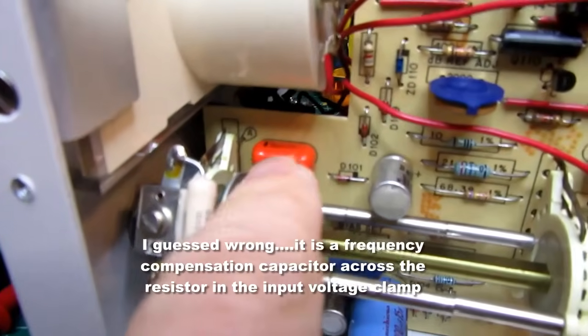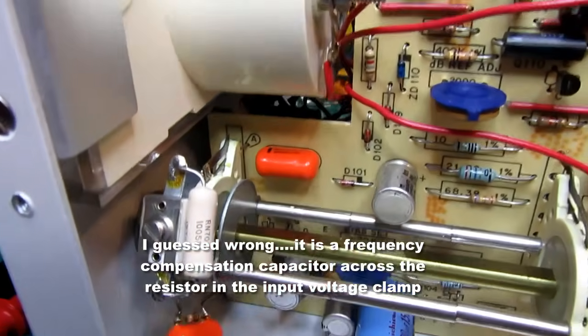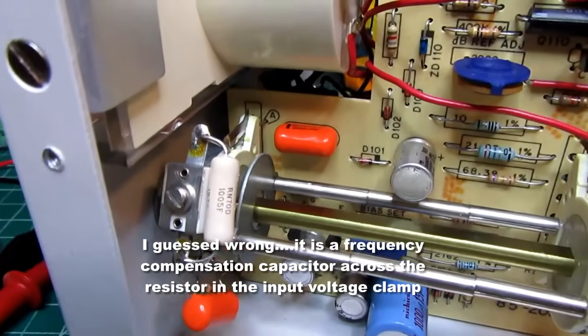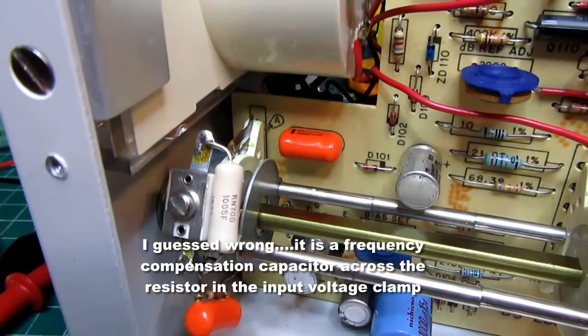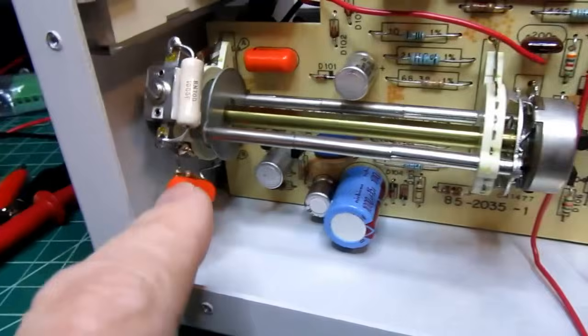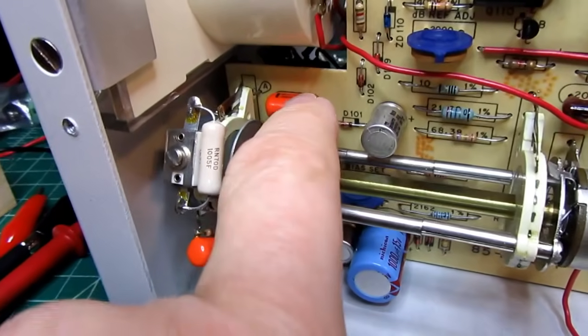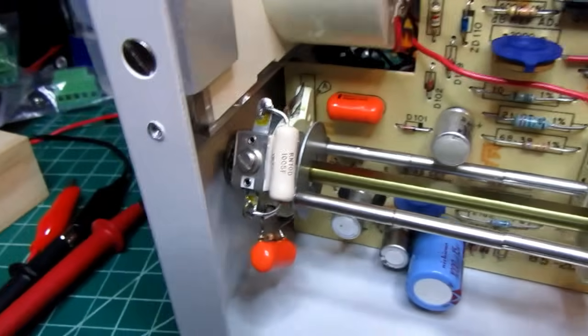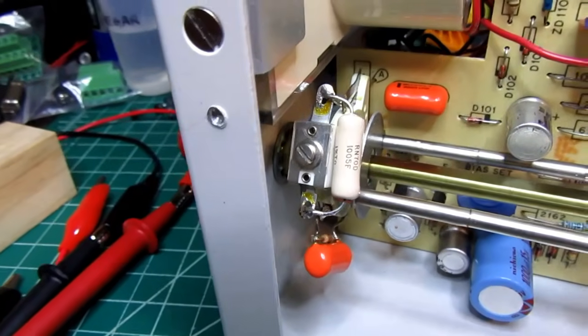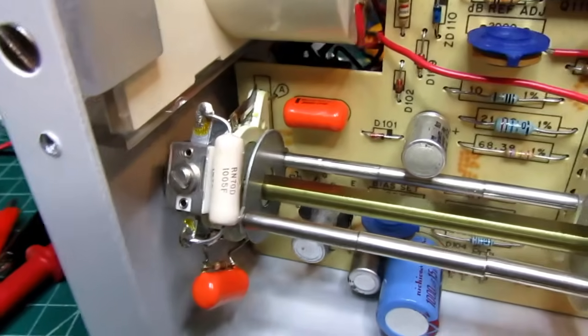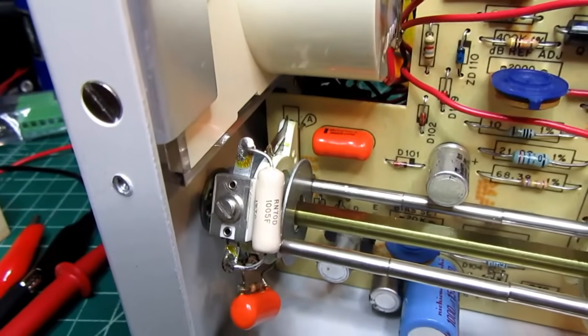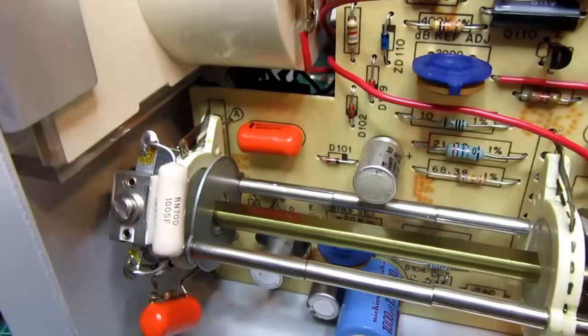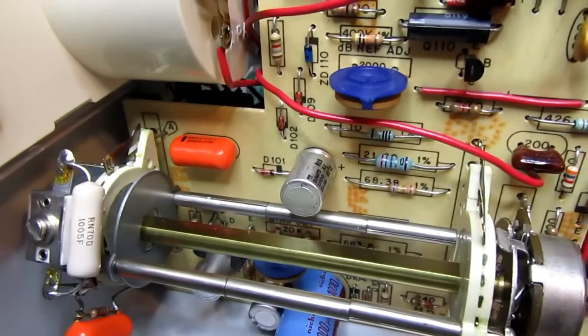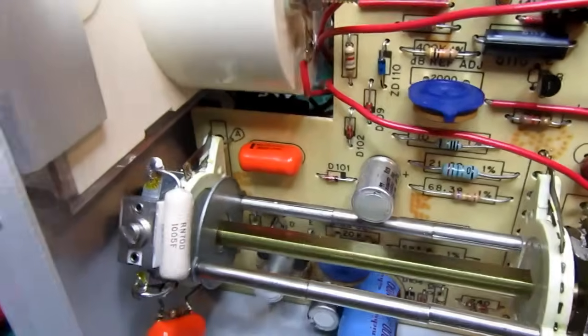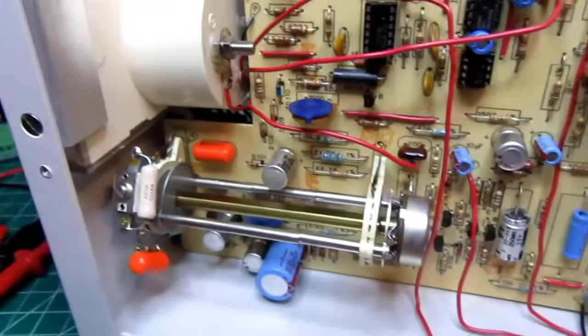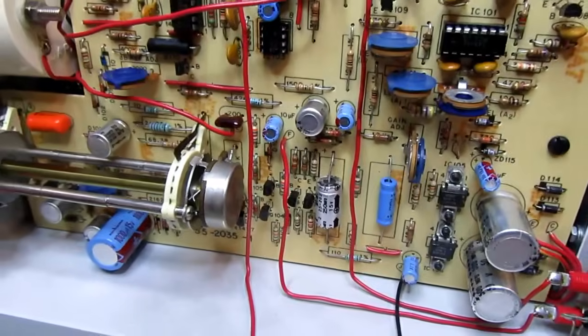This capacitor here is probably going to be the input coupling capacitor, which blocks any DC component of the input signal and allows only the AC component through. This capacitor and this capacitor seem to be orange drop type, which are considered to be extremely stable in terms of their capacitance, and they don't change very much over temperature, although their exact value is not critical in this meter.